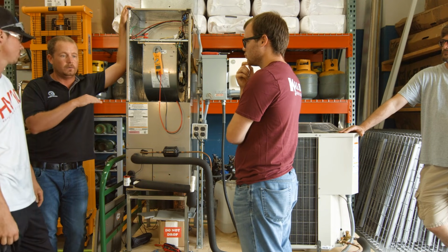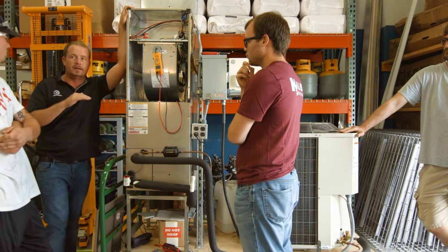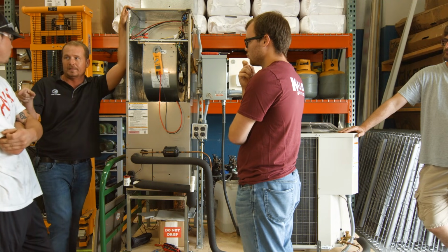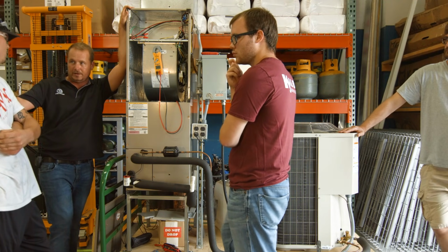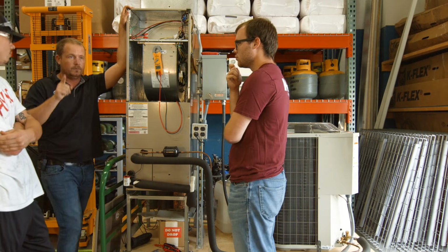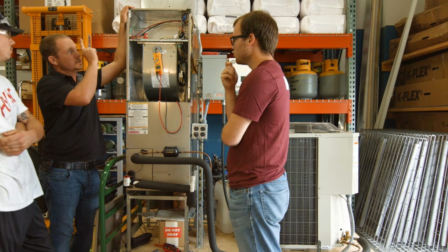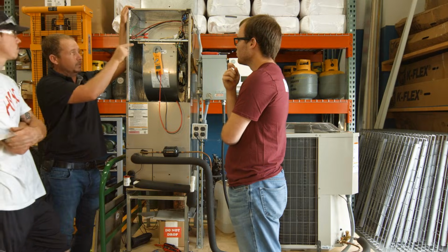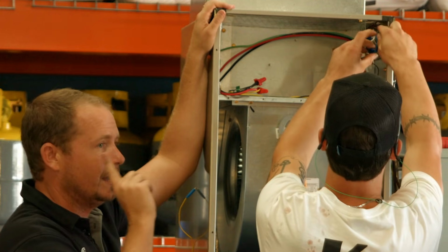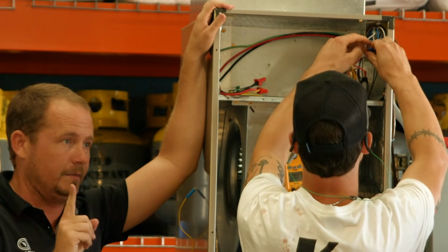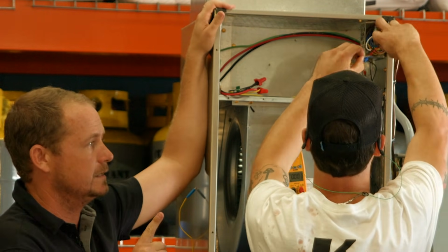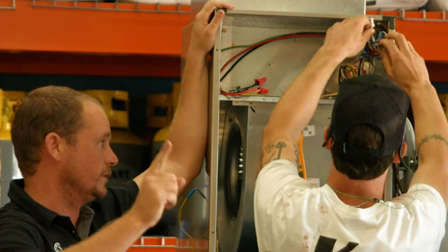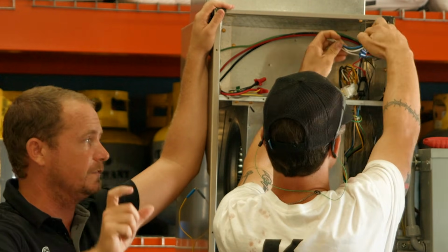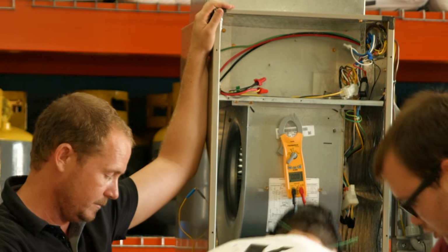I'm fine with where you started there, but don't wire nut them and ohm them out, because that's the test for an open, not for a short, and we're looking for a short right now. So I'd suggest do the same thing, pull them out, unhook them, but do not unhook common. We need to keep common intact in case that's where the short is, because that short blowing the fuse could be shorted to ground.